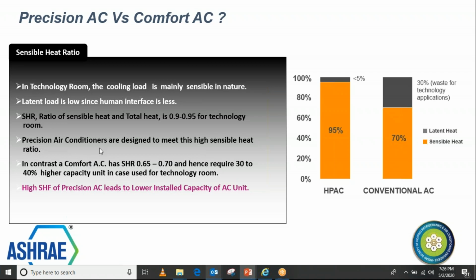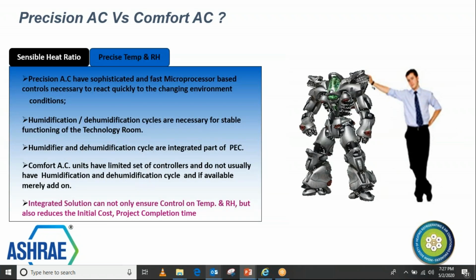And obviously, we will learn in the next slides how it makes a difference when you install more comfort capacity or less capacity, how it impacts the power consumption, and how it impacts the temperature and humidity in the room. So in this slide, the message to you is that it is very important to understand the heat load calculation and the sensible heat ratio, and based on that we have to select the unit. And when we move forward, obviously, the precision temperature and humidity control. Most of these applications, whether control rooms, textile labs, server rooms, data centers, hub rooms, telco rooms or switch rooms, demand precise control of temperature and humidity.